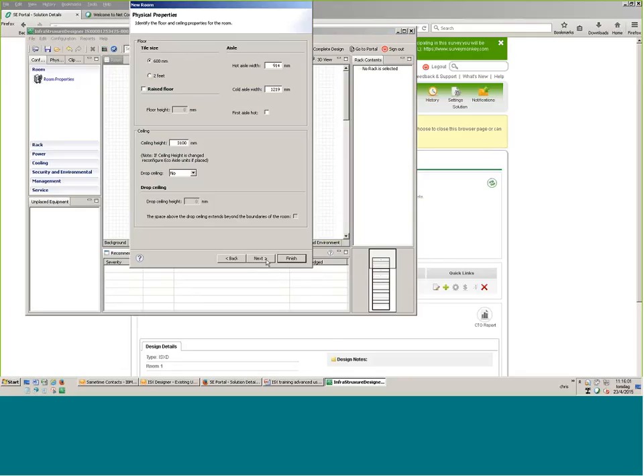Physical properties are something we need to know. Hot aisle width generally, if we make it equal - we can change that again - but in general it's 3 feet here, and you can change this. Raised floor is very important to know if we have one or not, otherwise we don't know if we can do piping or not.